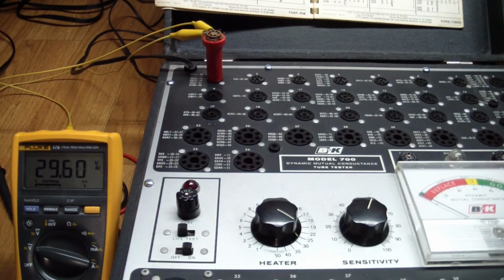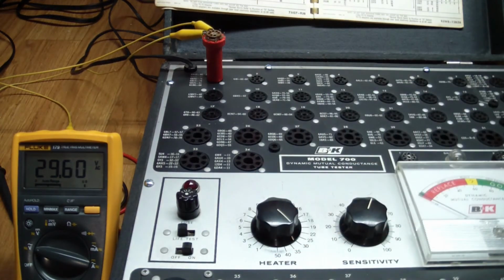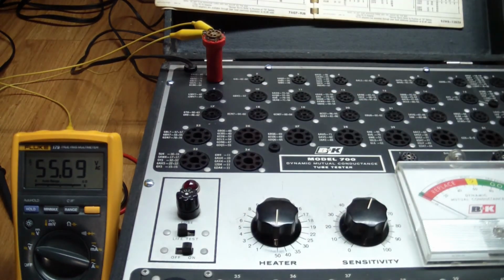The 25 and 30 also share a tap, which is listed at 27.9, and that shows up as 29.6. Again, in the range of 10% higher, and if we go to 30, that voltage should stay the same because it's the same tap, and it does. And finally we go to the highest, which is 50, and 50 listed on the schematic shows up slightly over 10% higher than spec'd. So it looks like the heater voltages are good.